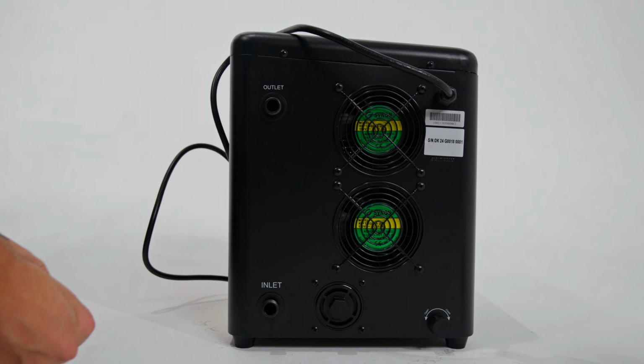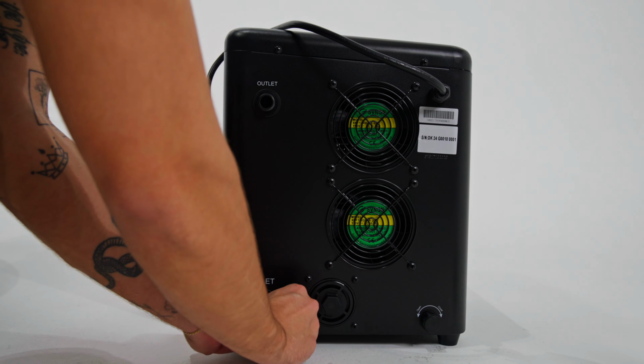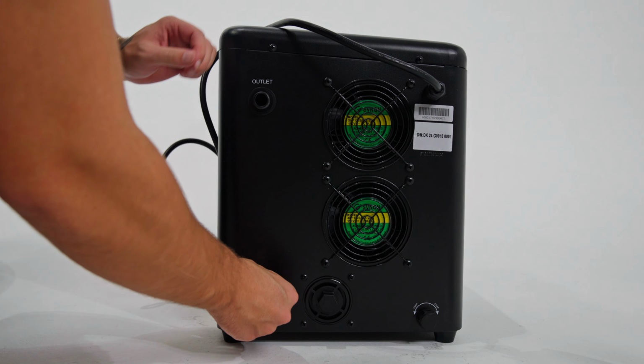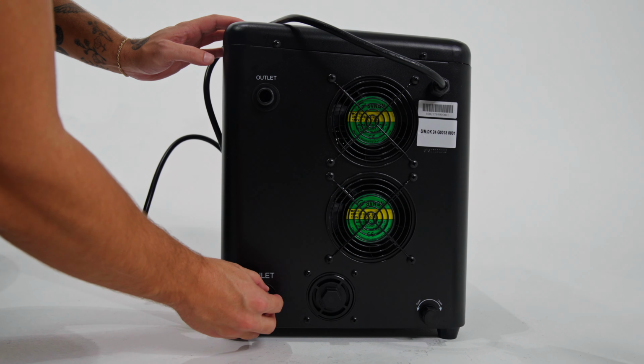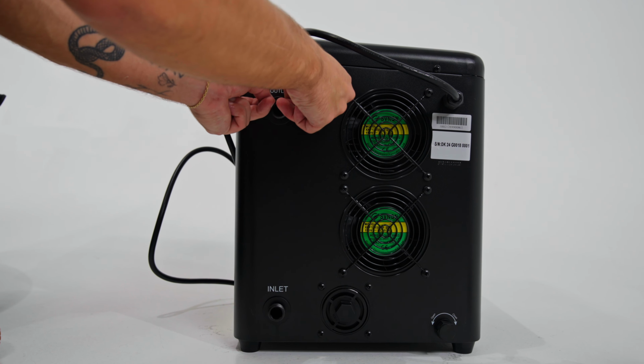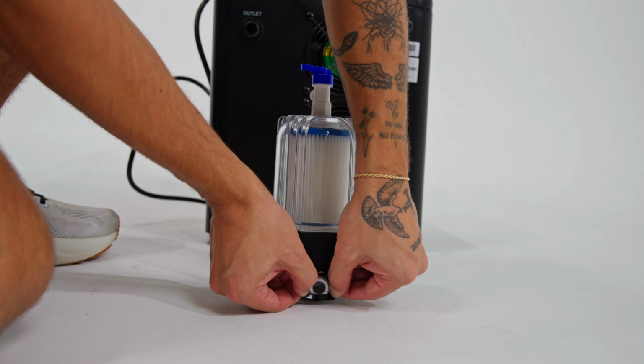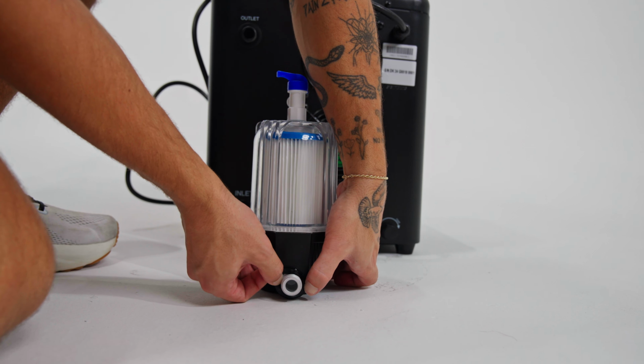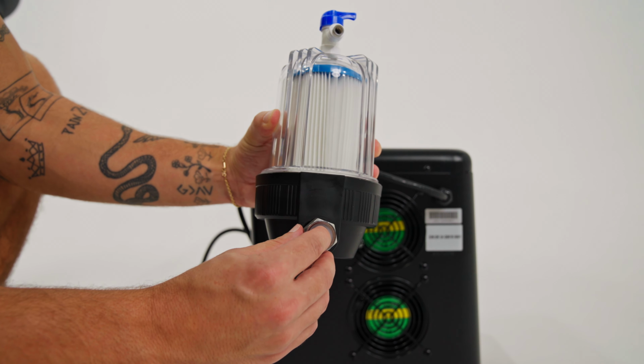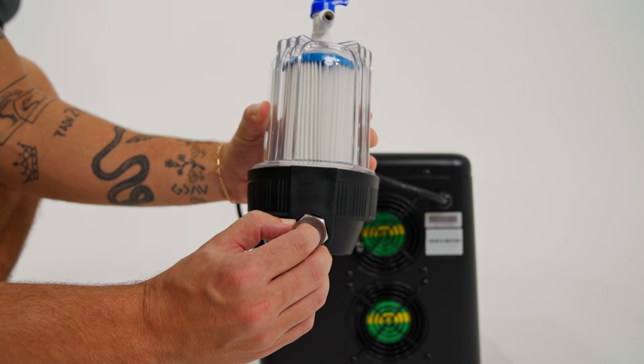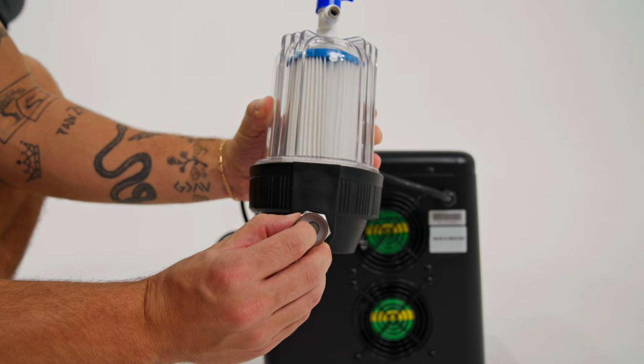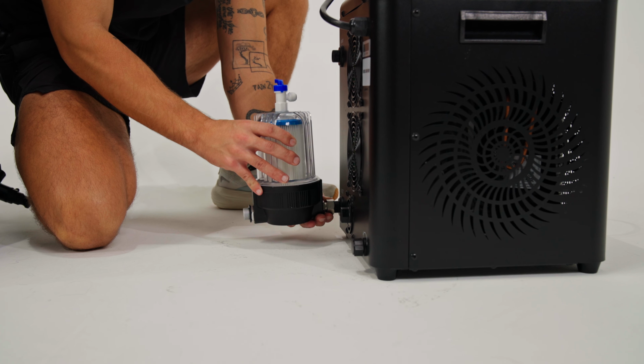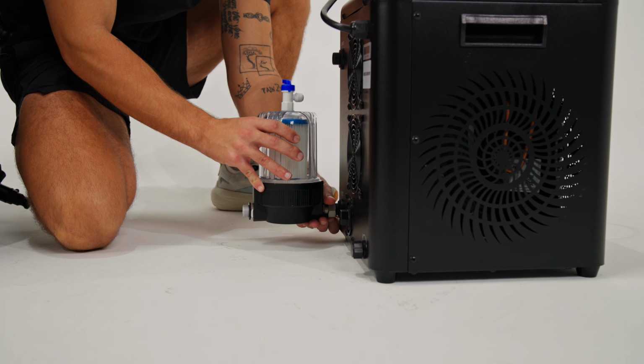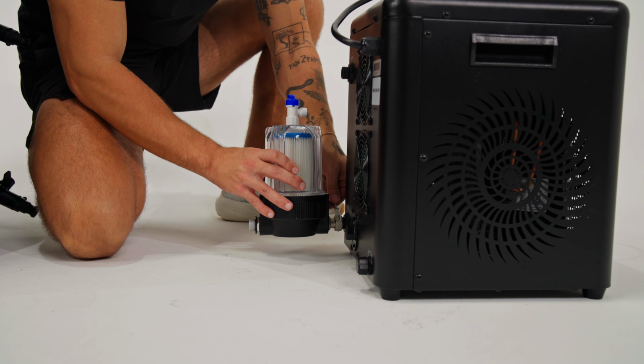Before we install anything else, take the 3 remaining black gaskets and install them now. One goes on the inlet port of the chiller, one goes on the outlet port, and the last one goes on the filter canister's threaded outlet. Then place the white gasket inside the open port of the filter canister, lightly pressing it in so it sits centered. Lastly, screw the canister onto the inlet port and tighten it with the included wrench until snug.